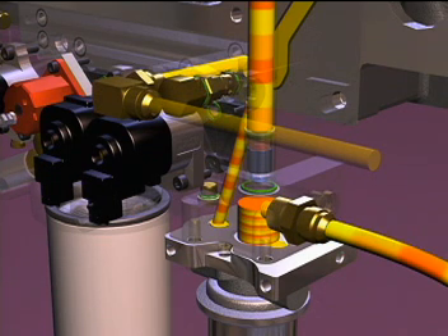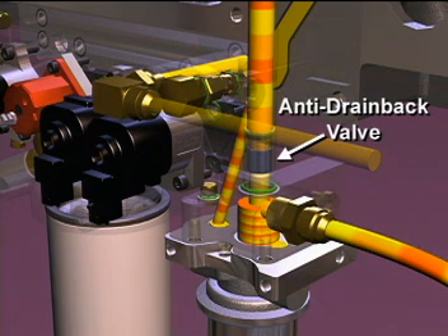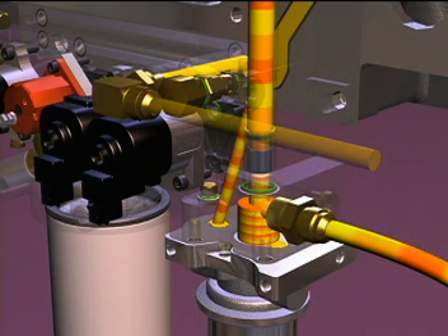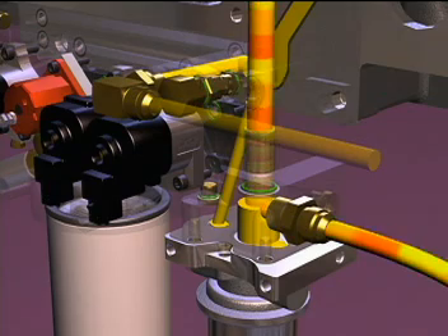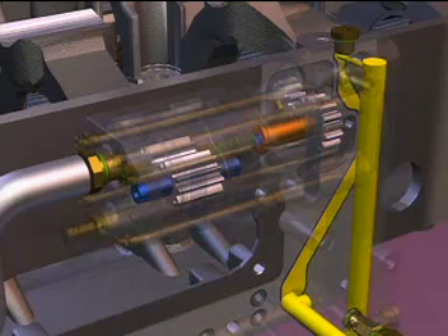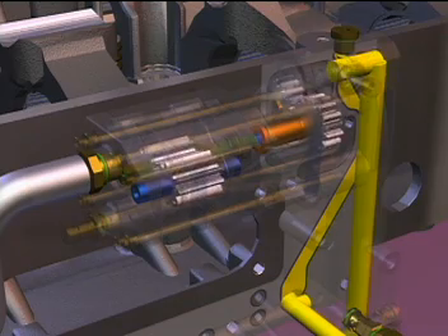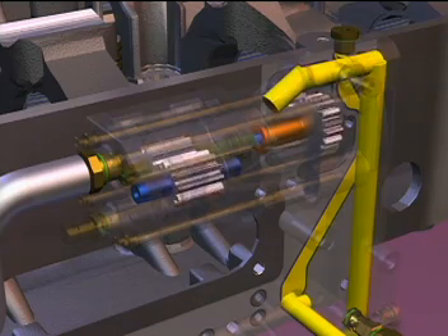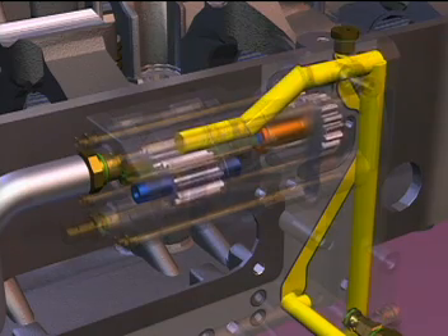When the engine starts, the gear pump can draw fuel directly from the inlet fitting through the anti-drainback valve. After 2 minutes of operation, the lift pump shuts down. The gear pump then draws all of the fuel directly from the inlet fitting past the anti-drainback valve. The gear pump provides the high volume and constant pressure needed for the system to meter properly.